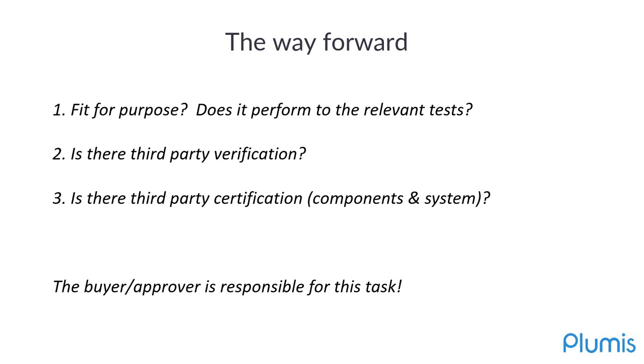and verifying that it performs to the relevant tests, and that those relevant tests will be replicated in an installation in the field in the form of correct bulbs, in the form of an adequate water supply. And then there's an improved level of verification, which is through third-party verification, where a third party has been involved in auditing the information provided by that first party. And finally, there is the ideal third-party certification of both components and system, which demonstrates that the whole componentry and system do perform as intended.